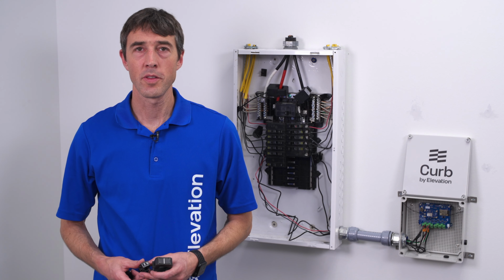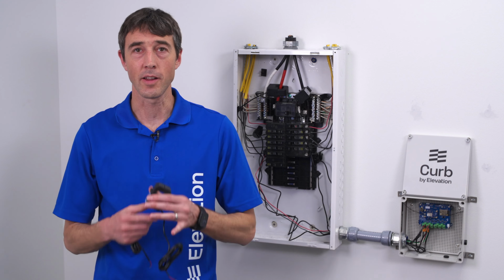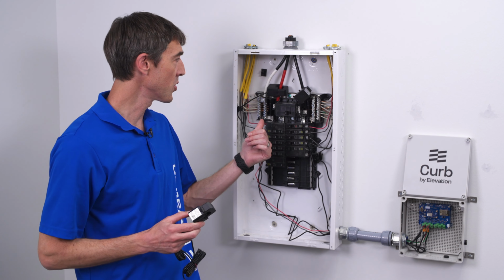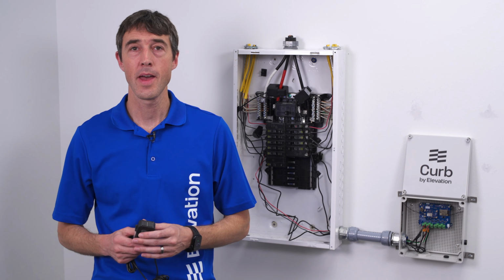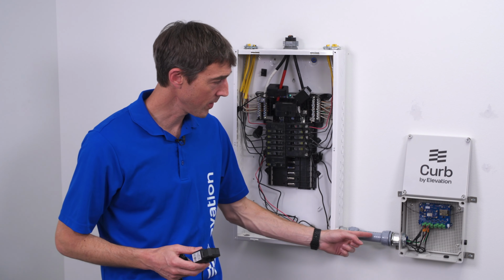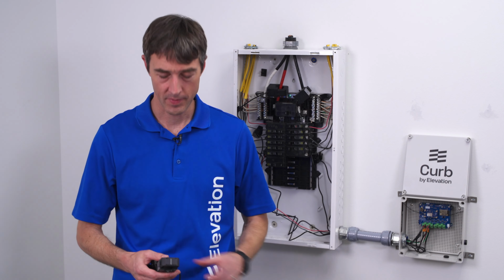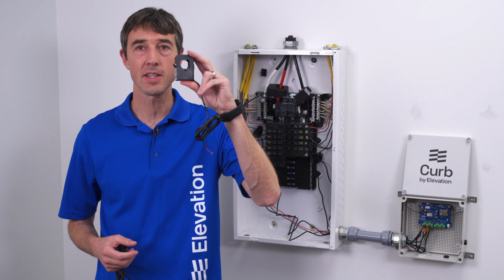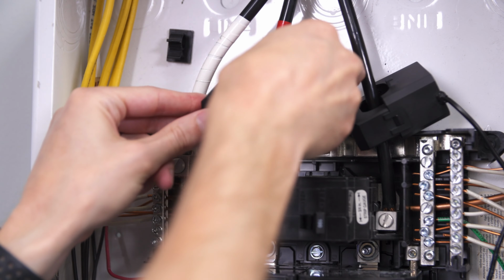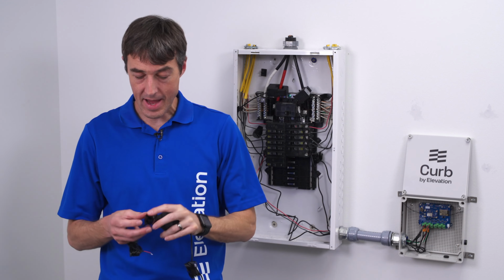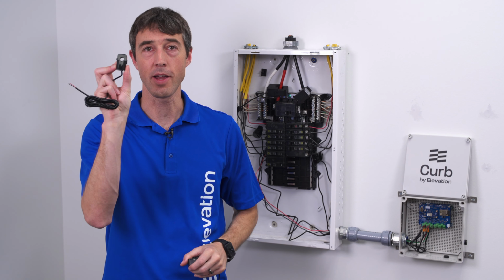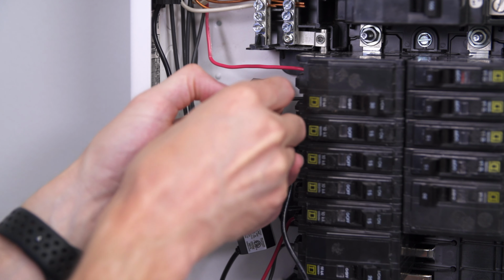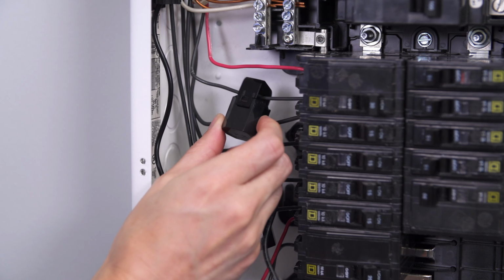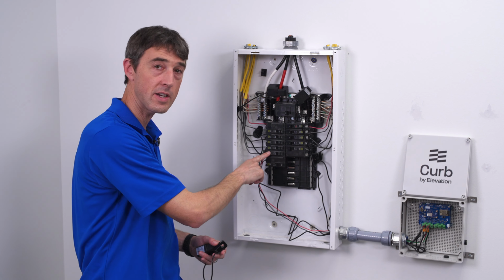Step 3 for installing the Curb device is installing the CT clamps or sensors on the individual wires inside the electrical panel, and then feeding these wires through the conduit and into the Curb device itself. There are 2 100 amp CT clamps. Those will go on the main power for the home, line 1 and line 2. There are 8 smaller 30 amp CT clamps that can go on the individual branch circuits, like solar, air conditioner, pool pumps, hot water heaters, and even sub panels.